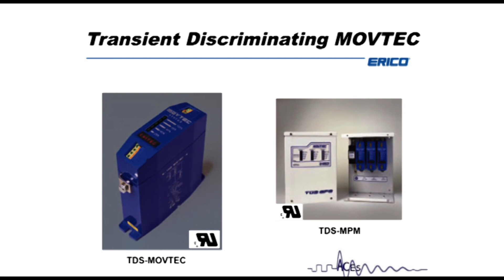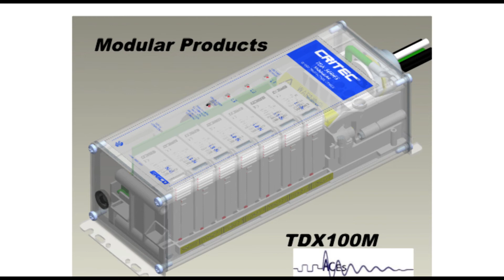So what we did about a dozen years ago was develop a modularised product that is packaged up in various forms. That's pretty much what we're showing there. It's a TDX100M. Those same TDX modules, those transient discriminating suppressor modules, can be used in 200 kA devices, 50 kA devices, so for main switchboards, very exposed main switchboards, down to DB level, smaller products as well. But the same building block, same MOV, thermal fusing, and transient discriminating technology.